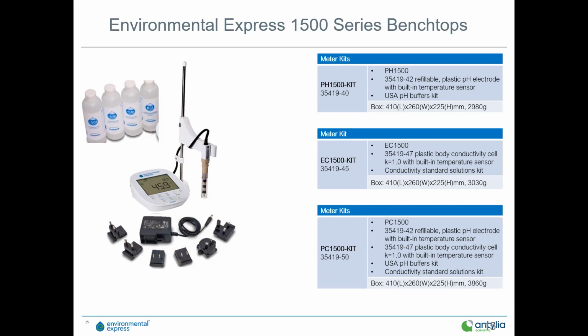We offer, again, the kit format, which is pictured here. You get the meter itself, the electrode stand, the sensor, the calibration solutions needed for that electrode, and the power supply with the 6 different plug configurations. Now, we also offer the 1500 series and our 2000 series with just the meter and electrode stand. That gives the customer flexibility to use different sensors. A little more challenging on the electrical conductance, because while it is a BNC, it does have a proprietary temperature curve. So you do need to use our sensor on that specific model. So those are the 3 basic kit formats: pH, electrical conductance, and PC.